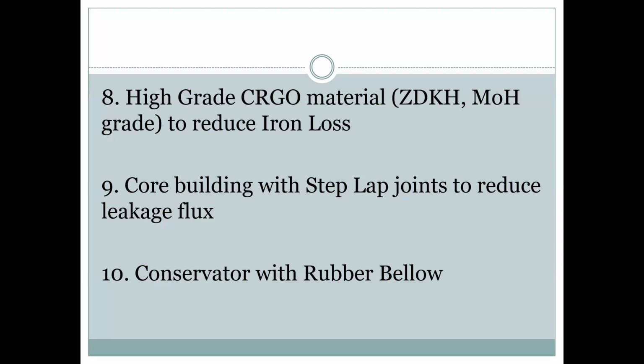High grade CRGO has come to reduce the loss, that is called ZDKH, and MOH grades, these reduce the loss. Core building by step lap joints, so leakage flux will be less. These are all the production activities where we can do this. Now, conservators are also coming with the bellow, so the exposure of oil to air is controlled by the air bellow. So air is not coming directly in touch with the oil in the conservator. So oil life goes up, and your filtration interval is increased.